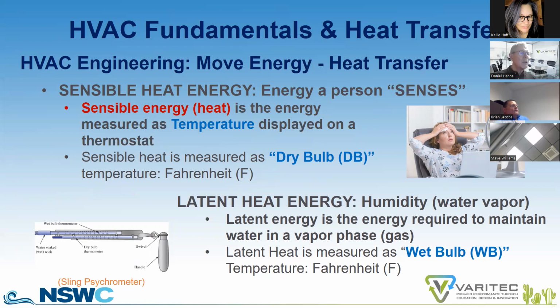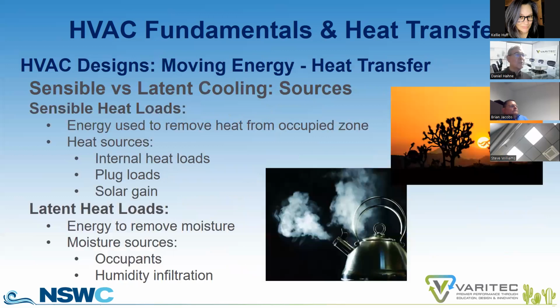What is latent heat energy? Latent heat is the amount of energy in the air necessary to maintain water in a vapor state. And there's humidity in every condition, whether it's at 90%, as we might see in the Southeast, or whether it's at 10% in Phoenix. There's always a level of humidity in the air, and it's the amount of energy present in the air that keeps water in a vapor state at that point. Latent heat is measured as the wet bulb temperature of a building. So you could say, if you want to control humidity, if you control the energy, if you remove the heat, you'll reduce the water that's able to stay in a vapor state.